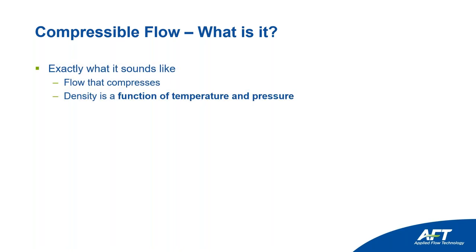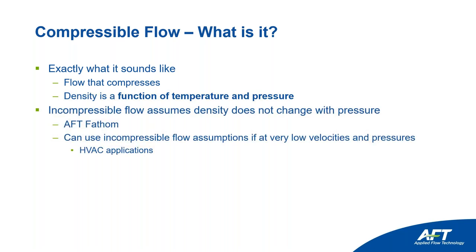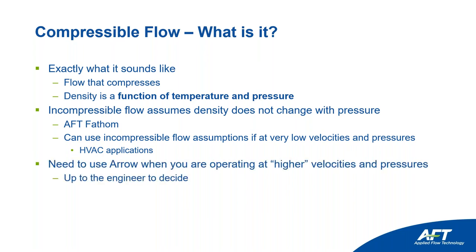So let's get into compressible flow. What is it? Well, it's exactly what it sounds like — it's flow that compresses. Specifically, density is a function of temperature and pressure, and you need an equation of state to figure out what your density is. Incompressible flow assumes density does not change with pressure. AFT Fathom models incompressible flow — usually liquids, and also low-velocity and low-pressure gases like HVAC applications — where density changes are pretty minor.